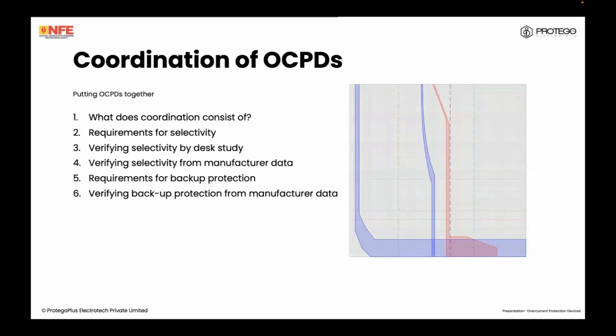Now, coordination. How do we get OCP? We have 2 OCPDs in a circuit or 3 OCPDs in a circuit. How do we make sure that only the one closest to the fault trips? That is selectivity. Then, if one OCPD is there and you have a fault downstream of that, and the fault current is greater than what the breaker or the OCPD can handle, how do we ensure that there's no damage? That is called backup protection or cascading. So when it comes to coordination, we look at what coordination consists of.